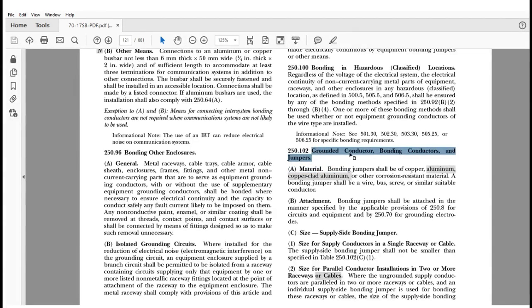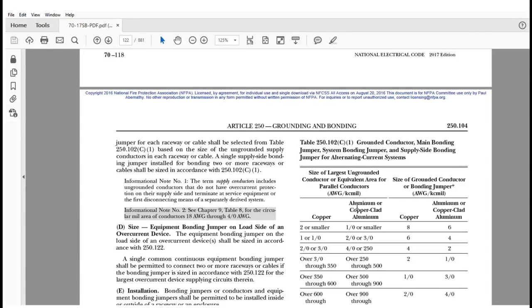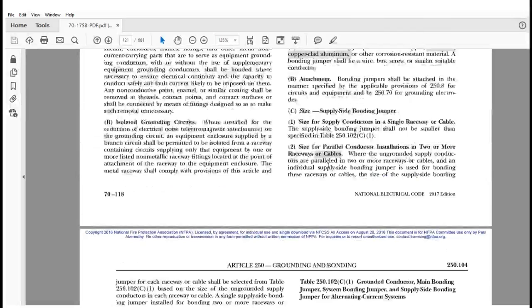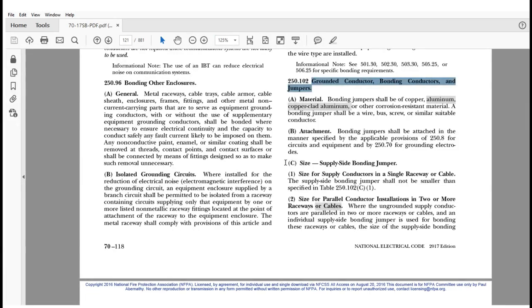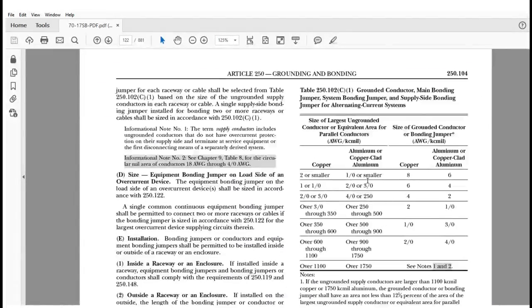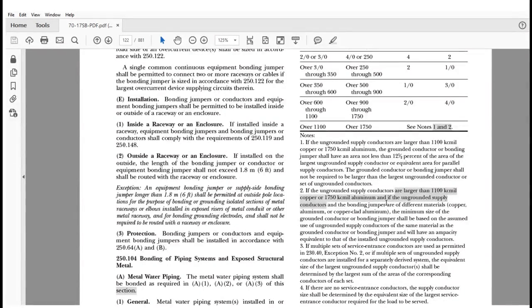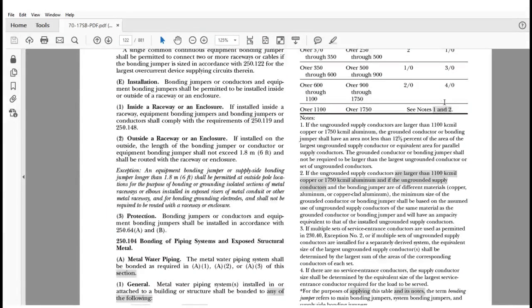And so the term grounded conductor was added here because this is how you size the grounded conductor, okay? Of course, it always has got to be at least the size of the calculated neutral load, or the grounded conductor load, but here it can't be smaller than table 250.102C1 as directed by code of 250.102C here. Okay? All right, so there's your table, there's your sizes, nothing really changed in that. That has any real significance other than it says here, see notes 1 and 2. Notes 1 and 2 are talking about when it's over 1750 aluminum, again 1100 kcmil, that you use a 12.5%, which is what you got when we had to go all the way back to 250.66 prior to 2014. So that language is all here. Okay, so that's pretty much the language.